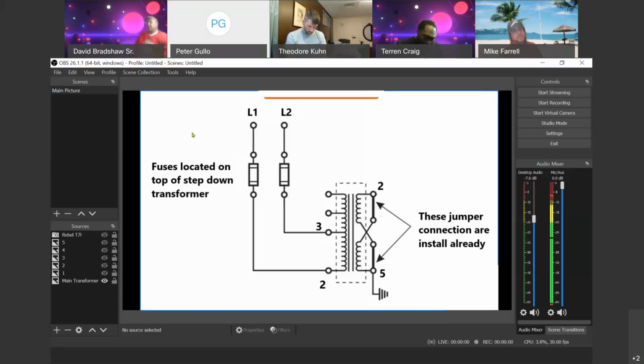Okay, so watch this. L1 and L2, I'm just going to talk about this. If we go across pin 2 and 3 and we don't get 208, we know we have to check the fuse. We need to check the input of the fuse because we know 2 and 3 are connected to the output of the fuse. So we go to the input of the fuse. If I go to the input of the 2 fuses on the top portion and I don't get 208, where's the problem? At the bottom? No, you're going the wrong way. It's got to be either L1 or L2. The fuse is inside there on the main panel. Remember how we're supposed to test first? Phase to phase, phase 1 to phase 2, 208, and so forth. If these fuses are good and we don't get 208, one of the fuses popped in the panel box.